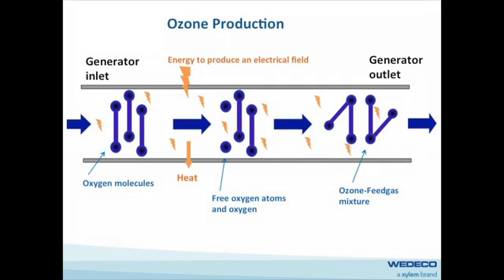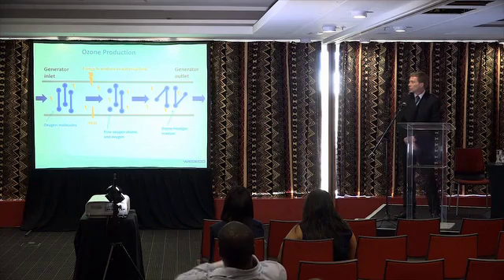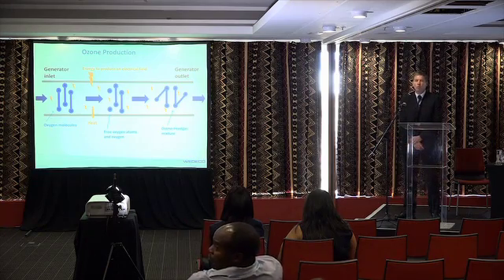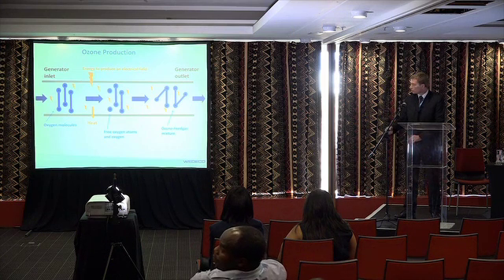As mentioned, it's generated through a discharge gap — you've got electrodes where you pass a stream of oxygen through with a high-intensity electric current, separating the oxygen molecules to form O3. You're only forming about 10% to 12% ozone in an oxygen stream. You don't really want to go much more than that — at about 16%, ozone starts becoming a bit explosive.